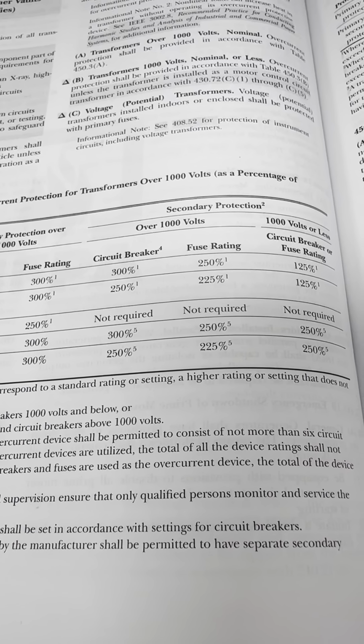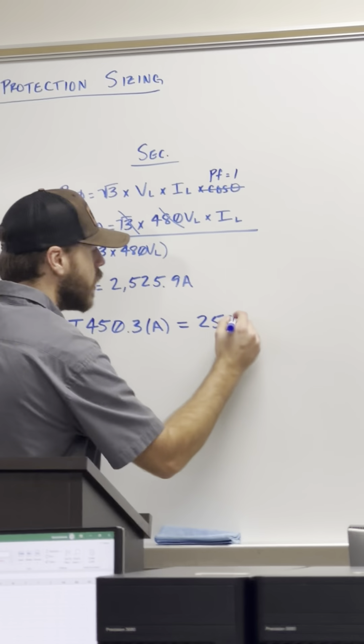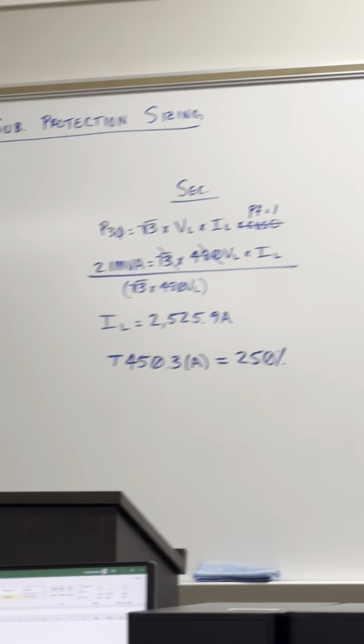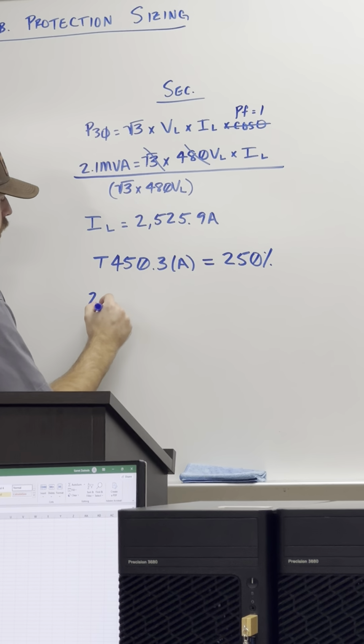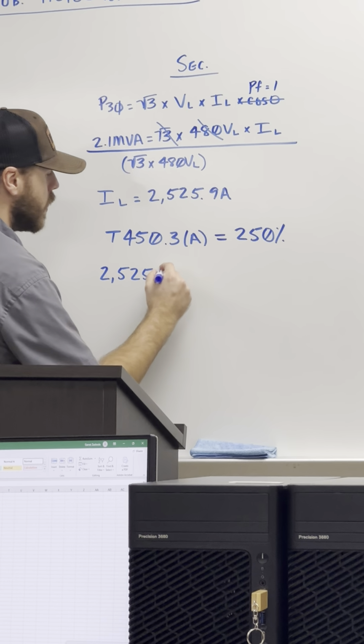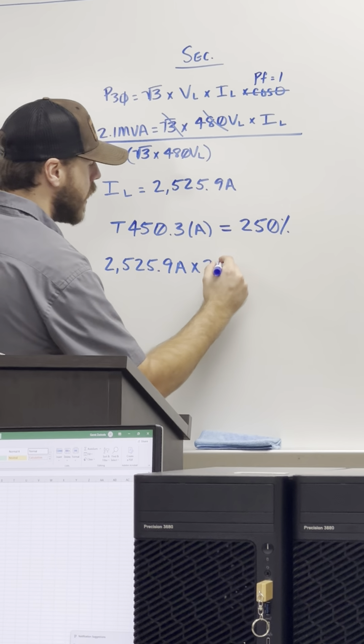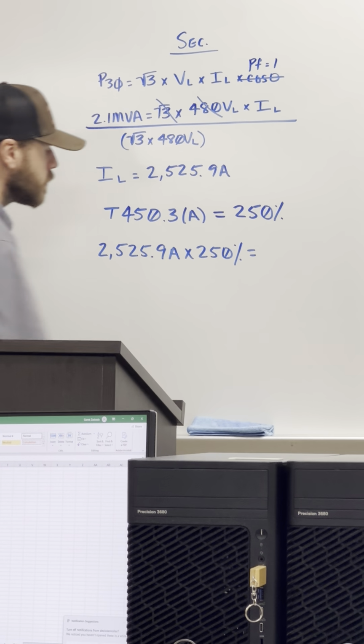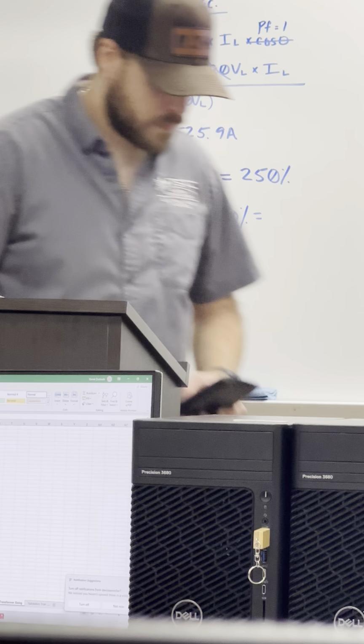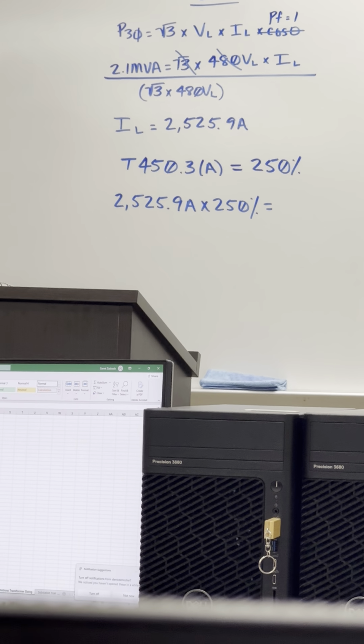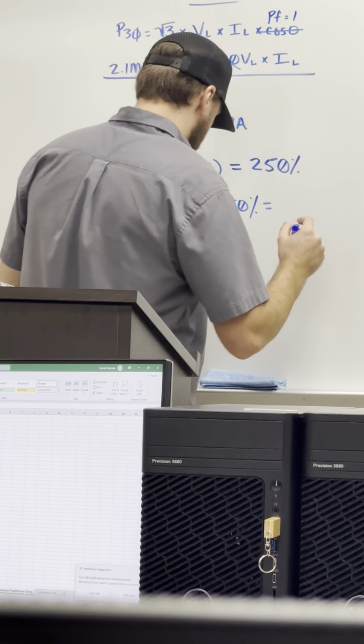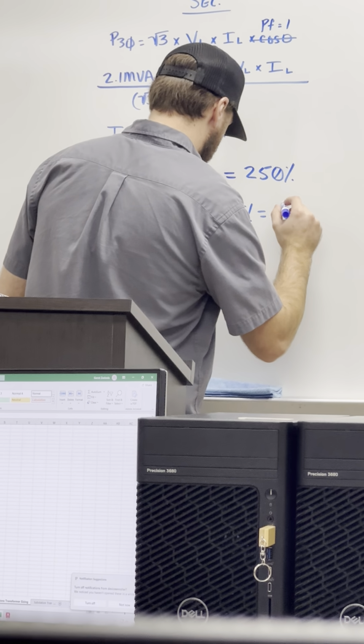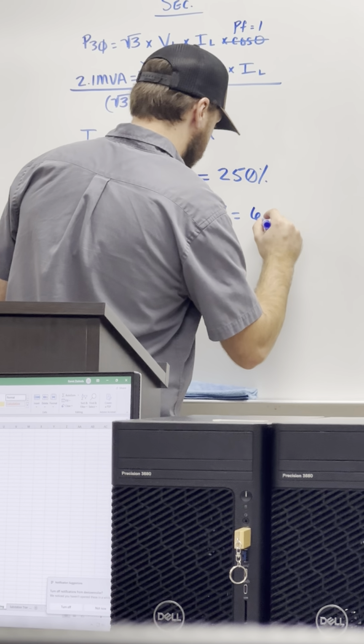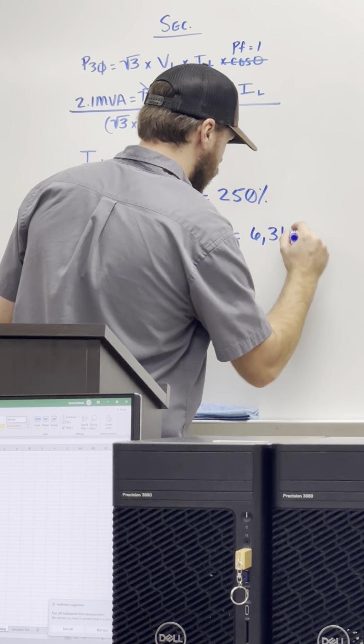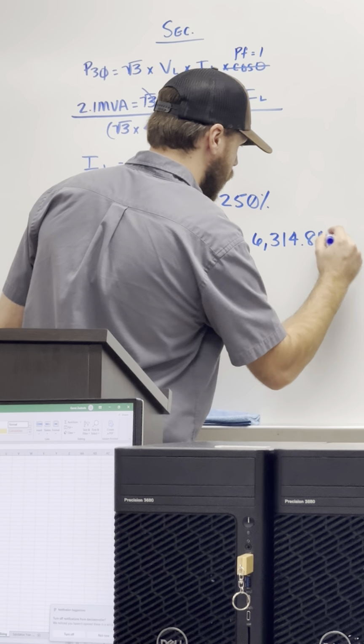So, kind of coming back over here to our secondary side, looking at this table, it told us that we need to take 250% of our transformer rated current. So I'm going to take this 2,525.9 amps and multiply that by 250%. Calculate. 6,314.8 amps.